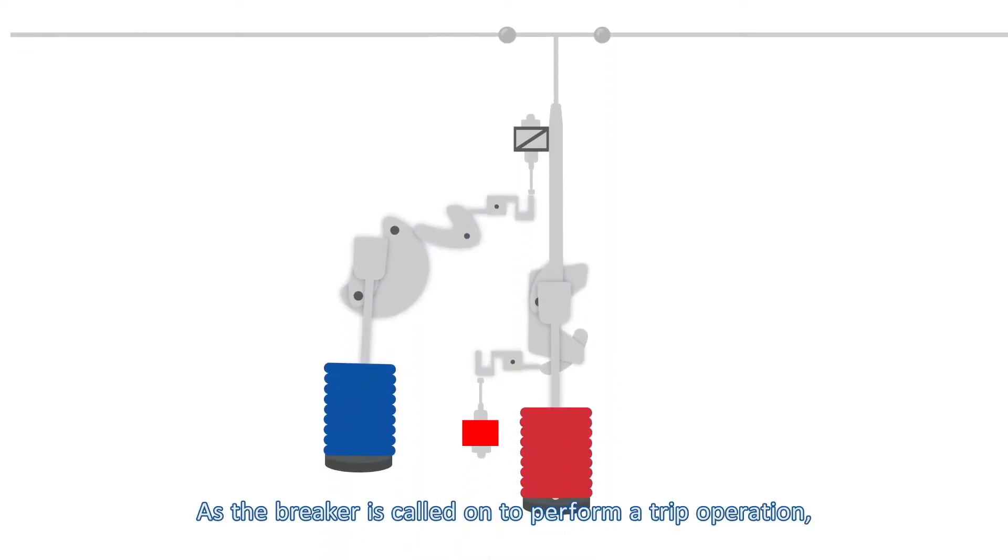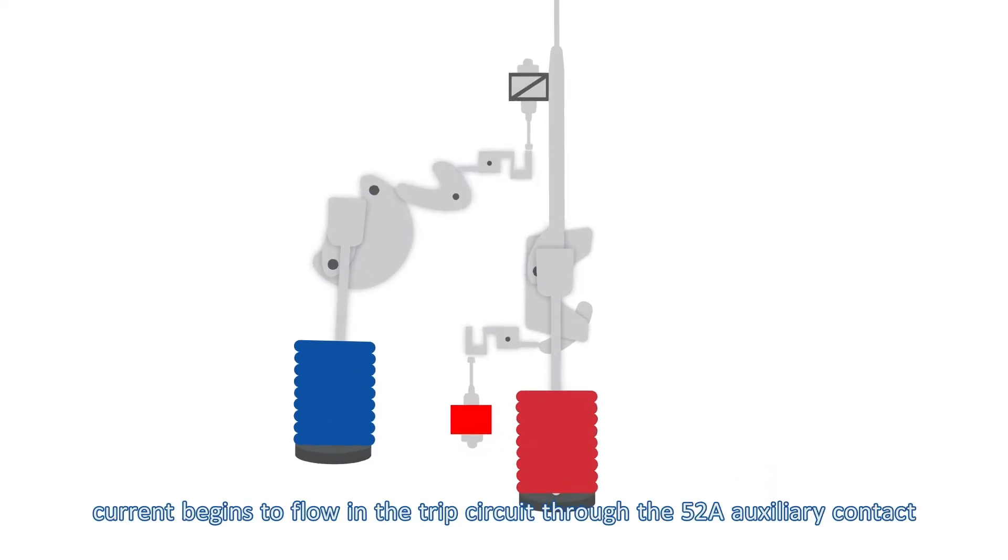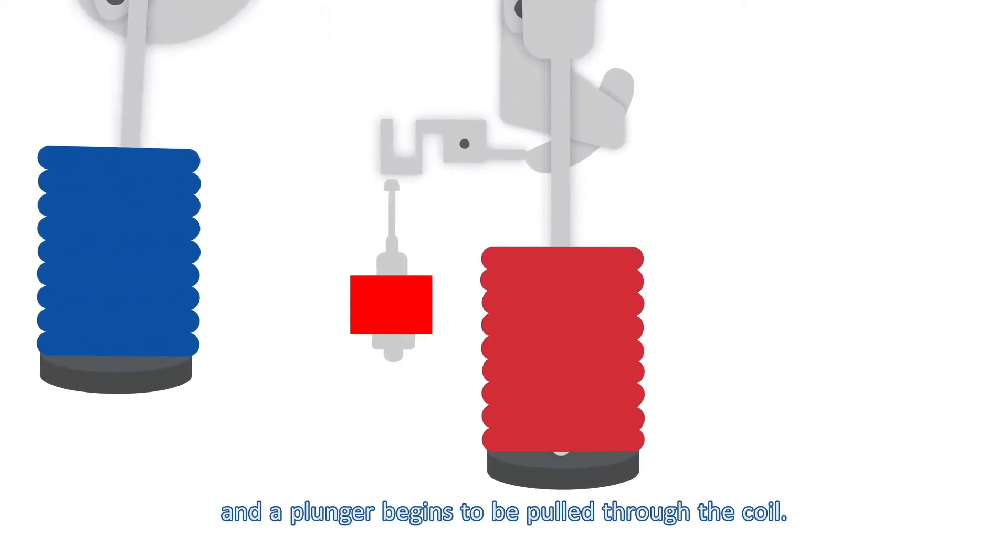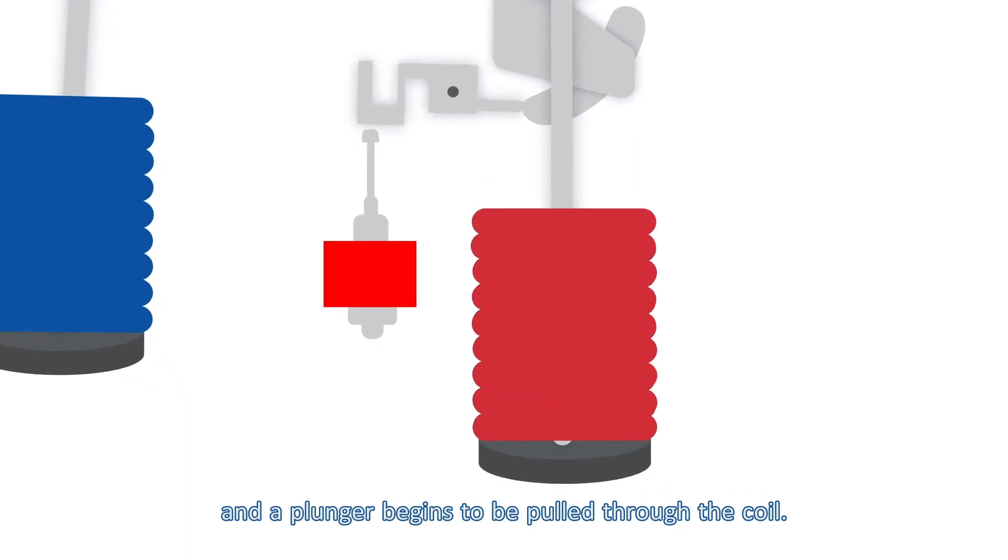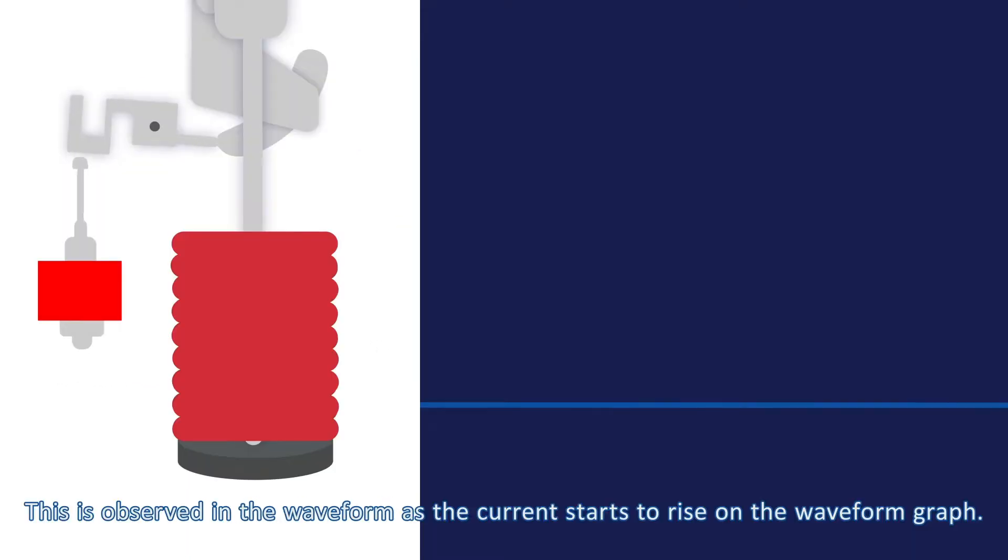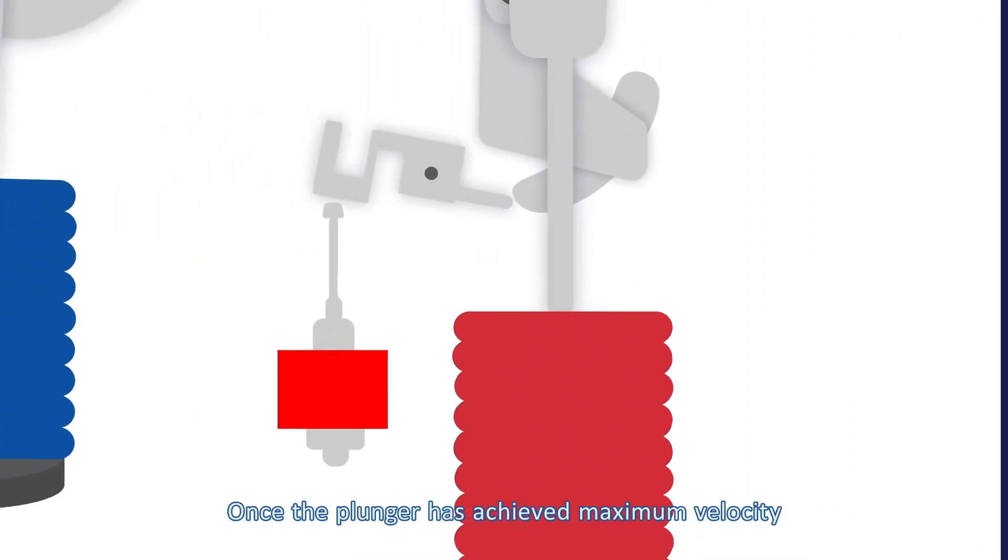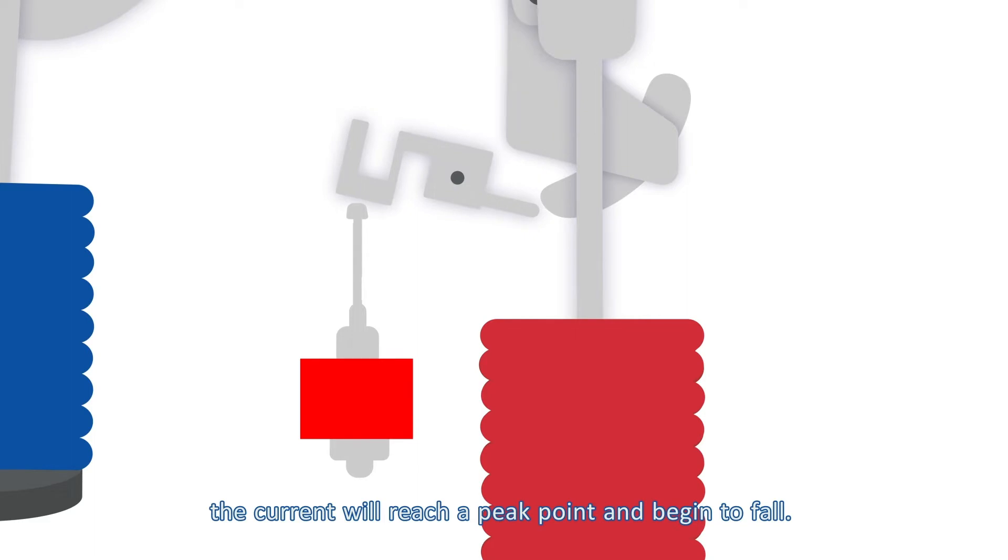As the breaker is called on to perform a trip operation, current begins to flow in the trip circuit through the 52A auxiliary contact and a plunger begins to be pulled through the coil. This is observed in the waveform as the current starts to rise on the waveform graph. Once the plunger has achieved maximum velocity, the current will reach a peak point and begin to fall.